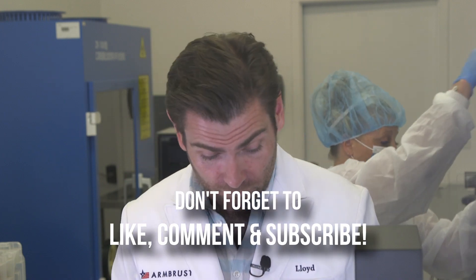This is a KF-94 style 3D mask — they say it's not a KF-94, as far as I can tell. You can tell with the packaging. Let her rip — this is a PFE machine, particulate filtration efficiency machine. We're doing the N95 tests almost the same way NIOSH does, using the same model machine: the TSI 8130A, the gold standard. This is going to output the efficiency in about 50 seconds.